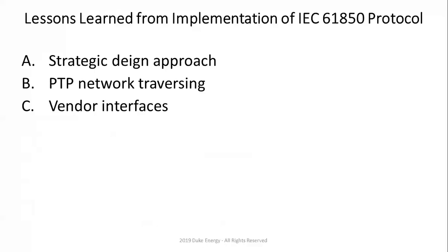So in this case, you put a merging unit right inside the breaker, transformer, wherever that is, and you don't run any copper wires. The only copper wires you run go to the merging unit. And then you run a fiber from that merging unit all the way over to the substation control house. Then you take another relay over there, and that's when you convert those signals back to analog, right? So that significantly reduces the amount of copper that you have to run, because some of those copper runs are over 1,000 feet, et cetera, because in a particular substation, you can have 10, 15, 20 breakers that are far away from the house, right?